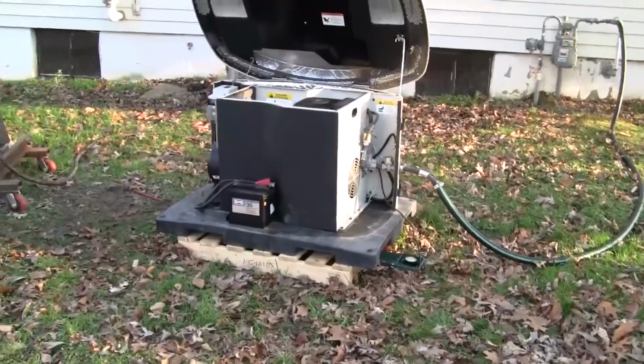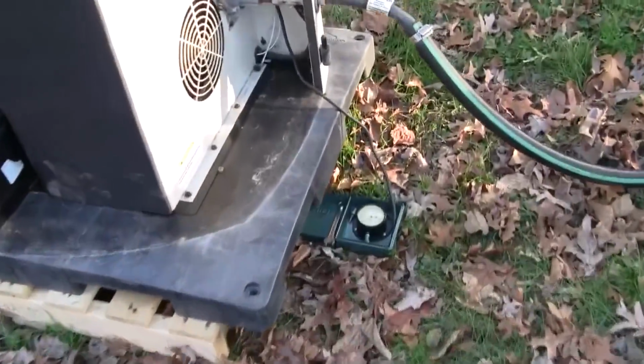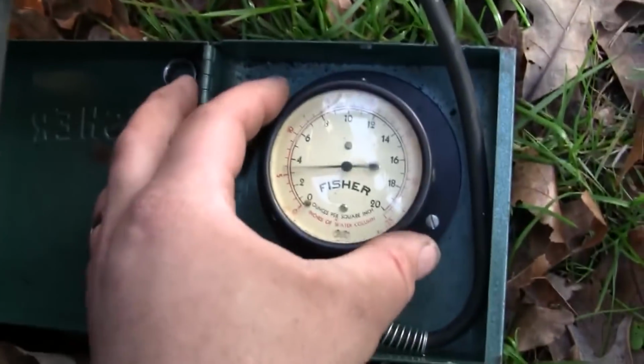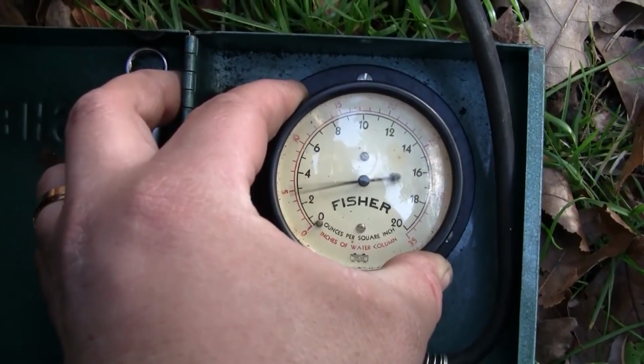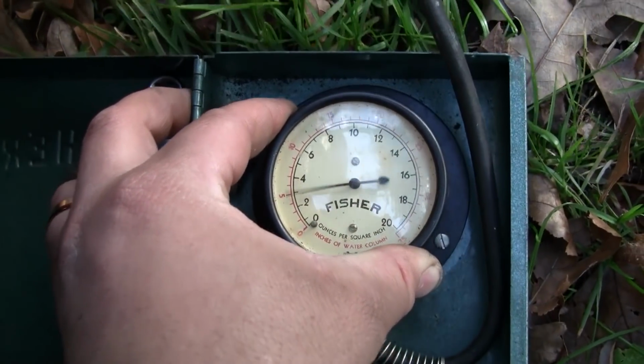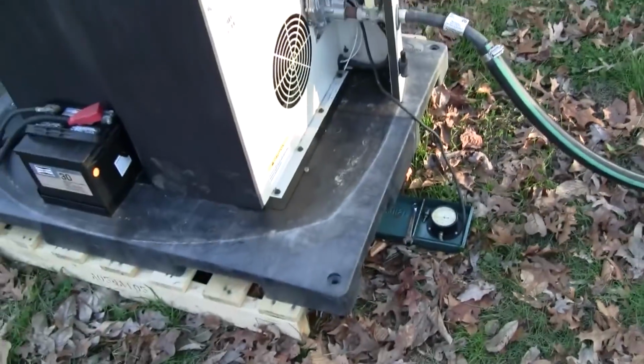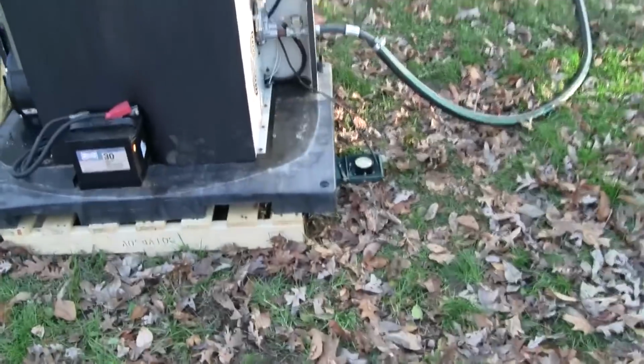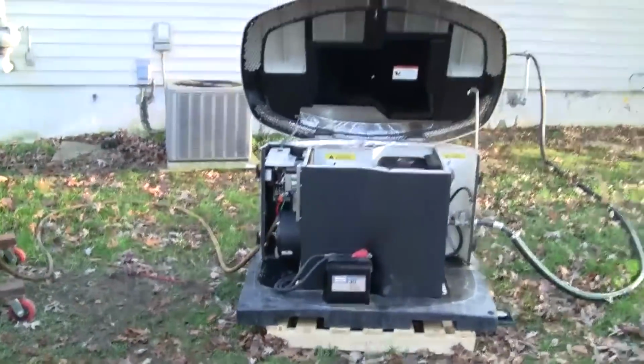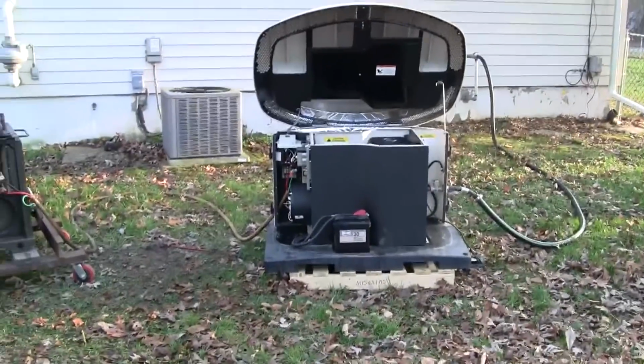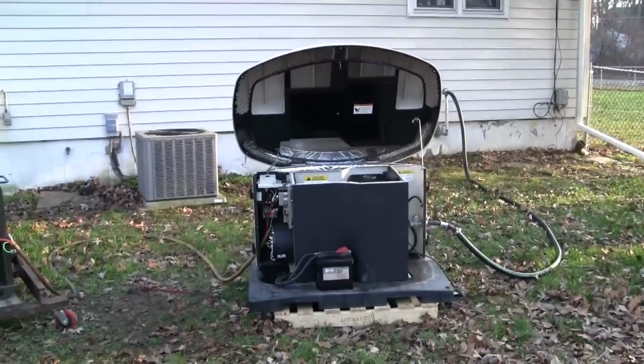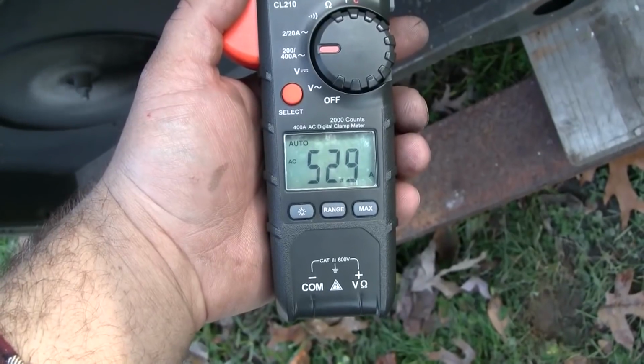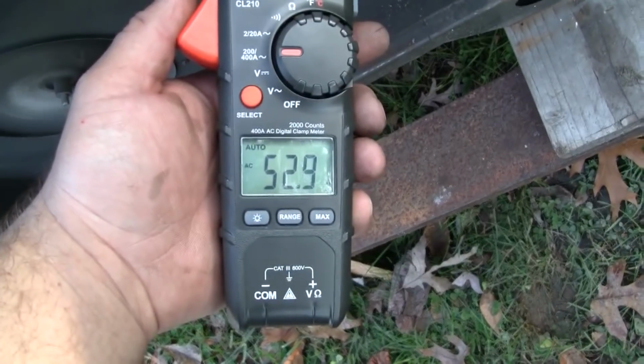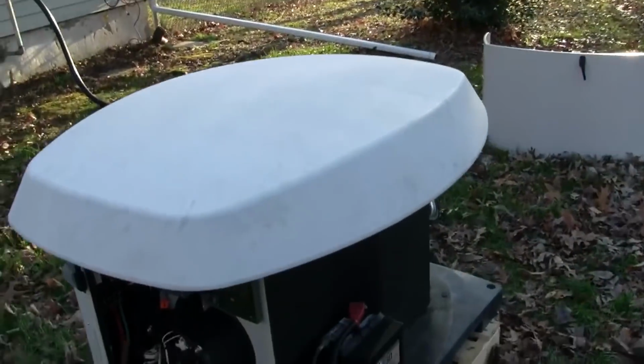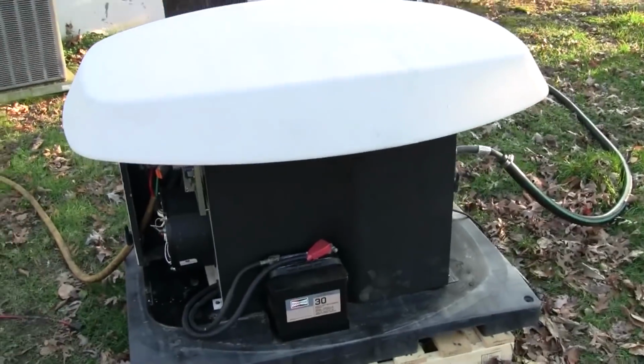It seems pretty happy. Let's see what the gas pressure's doing. Dancing around between 4.5 to 5.5 inches of water. So I'm going to say we're just over 50% load here. I'm going to say my gas meter is a little undersized to run this thing. I've been at 53 amps for about 5 minutes now. I lowered the lid on the enclosure. Seems to be doing quite well.